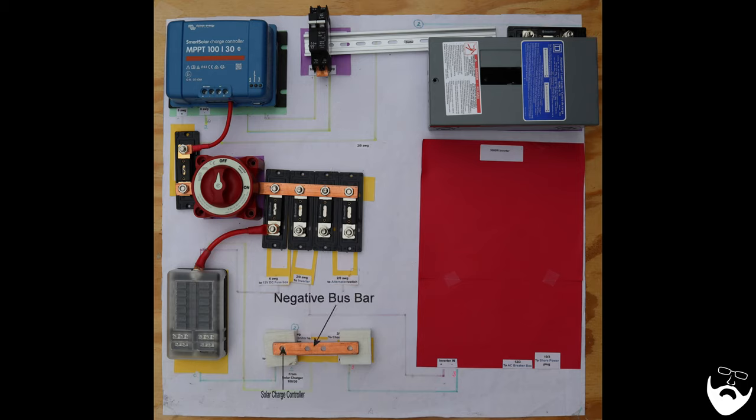Looking at the negative bus bar, an 8 gauge wire comes from the solar charge controller to the bus bar. A 6 gauge wire goes to the DC fuse box. A 2/0 wire goes to the battery monitor and onto the batteries.